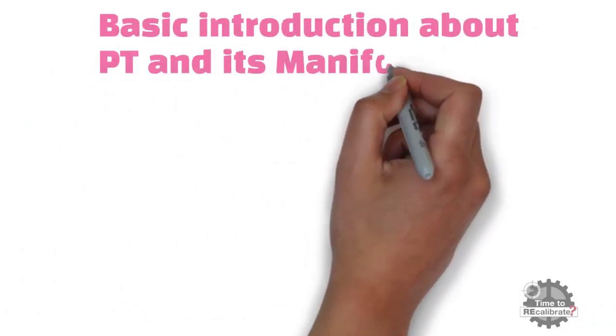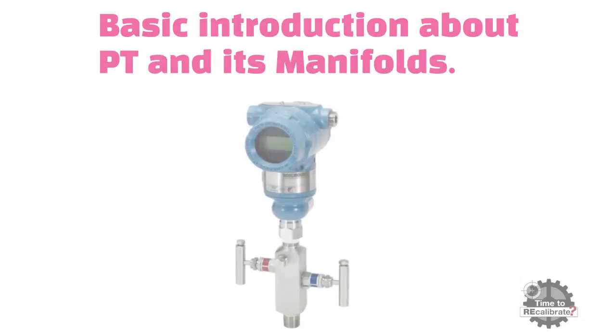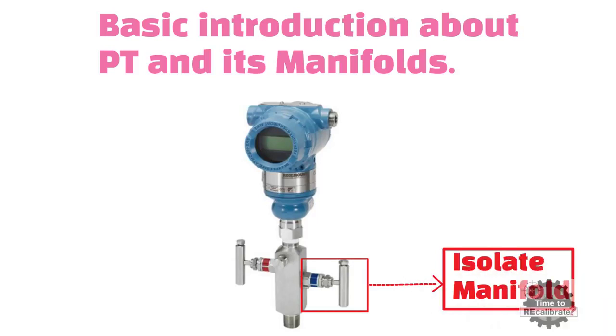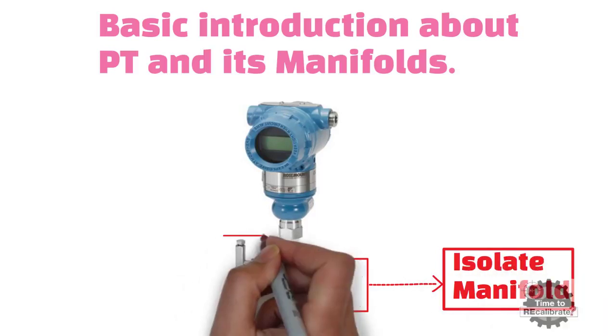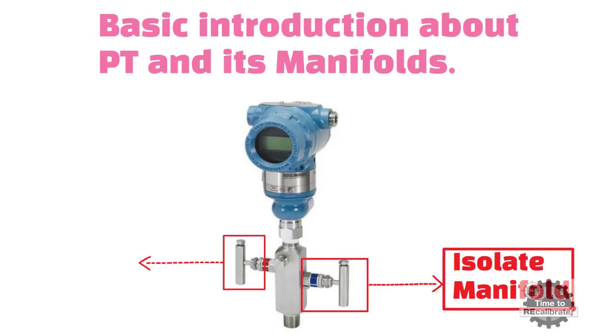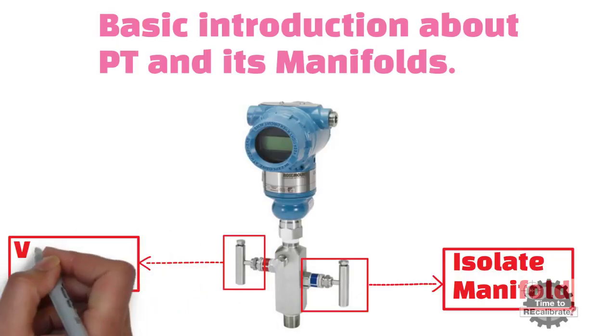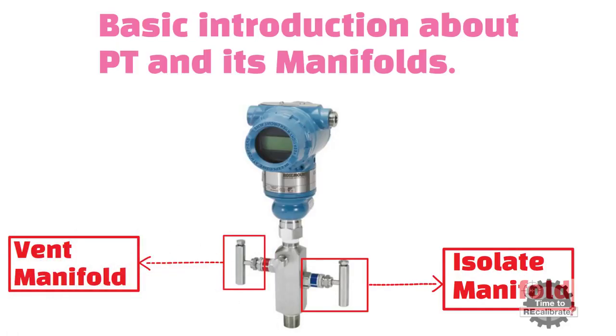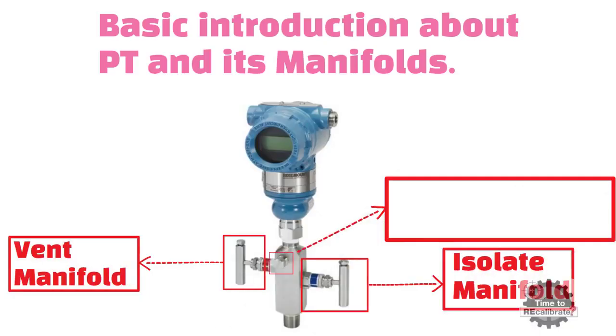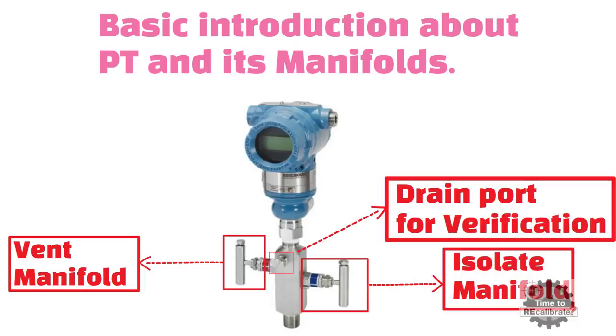Basic introduction about pressure transmitter and its manifolds. All pressure transmitters have two manifolds, and one drain port for verification or calibration. Bottom manifold is the isolate manifold, and it remains open in normal operation. Top manifold is the vent manifold, and it remains closed during normal operation. This middle port is the drain port, and this port is being used during verification time.